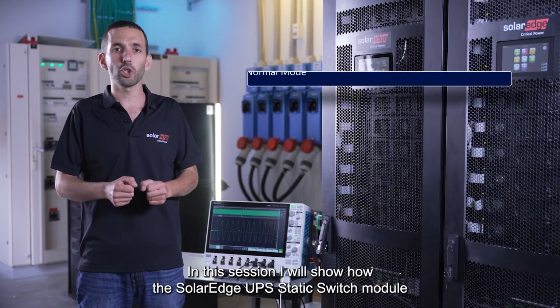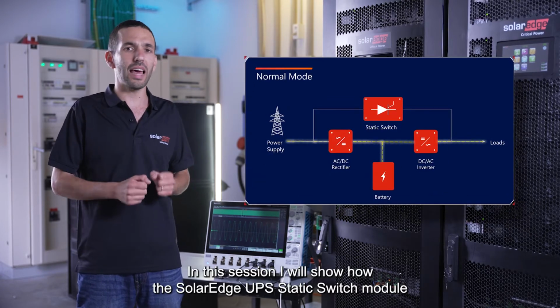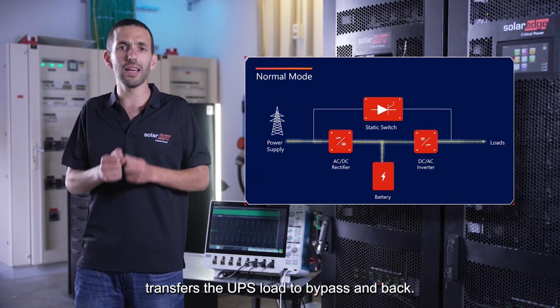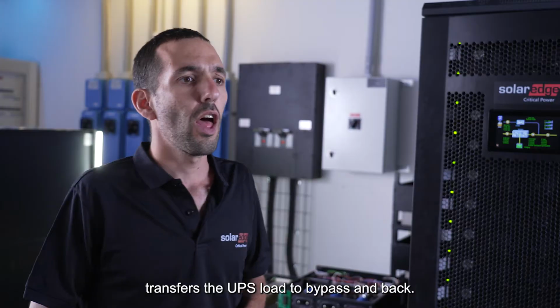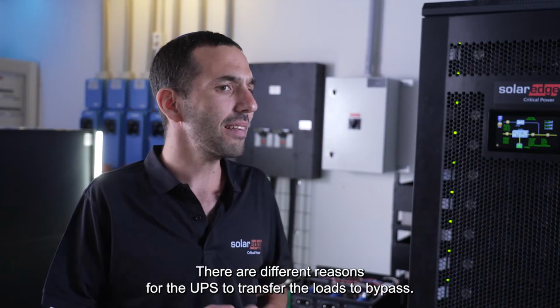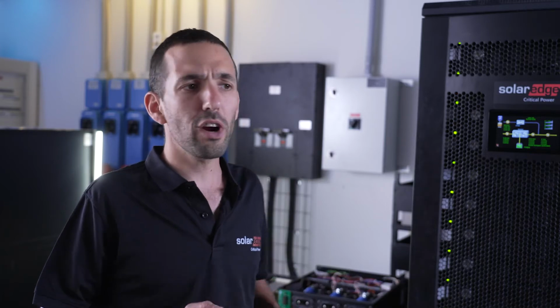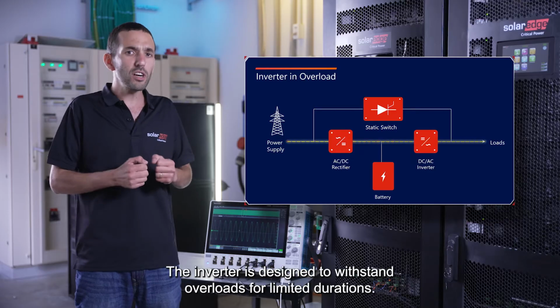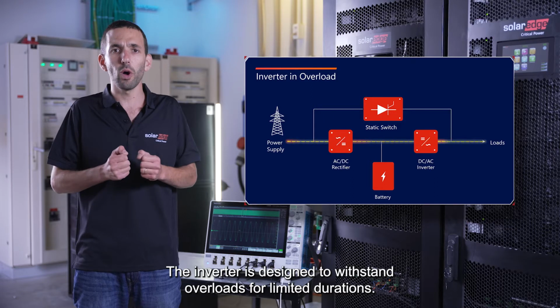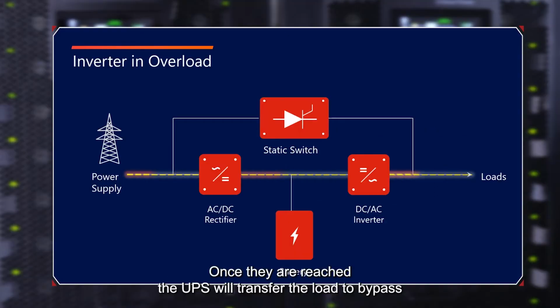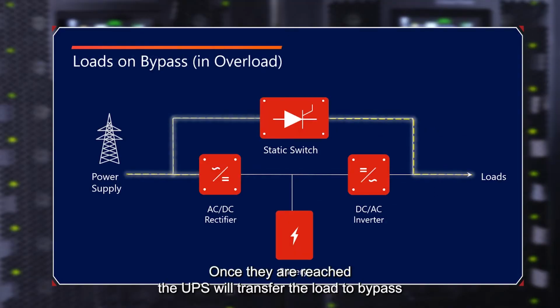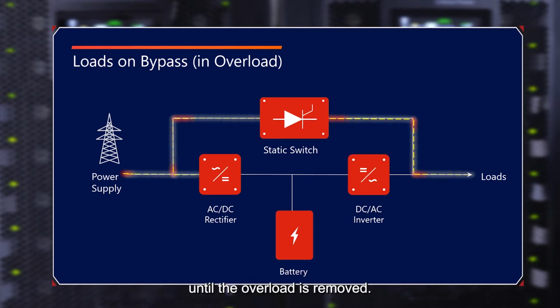In this session, I will show how the SolarEdge UPS static switch module transfers the UPS load to bypass and back. There are different reasons for the UPS to transfer the loads to bypass. For example, overload. The inverter is designed to withstand overloads for limited durations. Once they're reached, the UPS will transfer the load to bypass until the overload is removed.